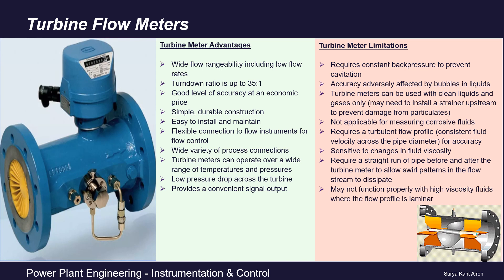They carry certain disadvantages: they require constant back pressure to prevent cavitation, and accuracy is adversely affected by bubbles in the liquid. Turbine flow meters can be used with clean fluids and gases only — it may be necessary to install a strainer on the upstream side to prevent damage from particles. They definitely cannot be used for corrosive fluids.